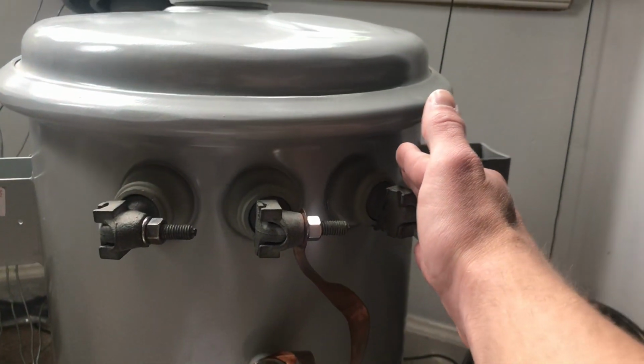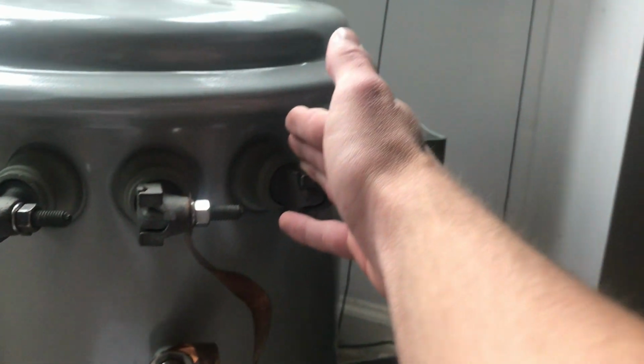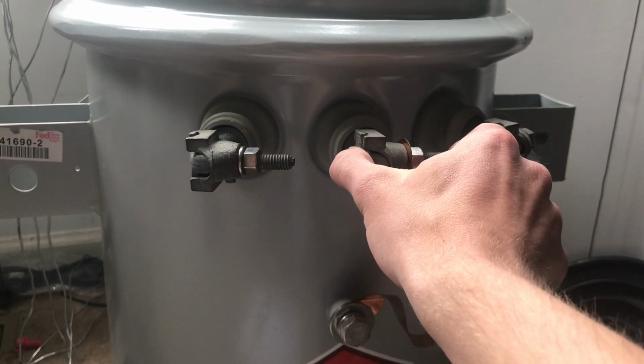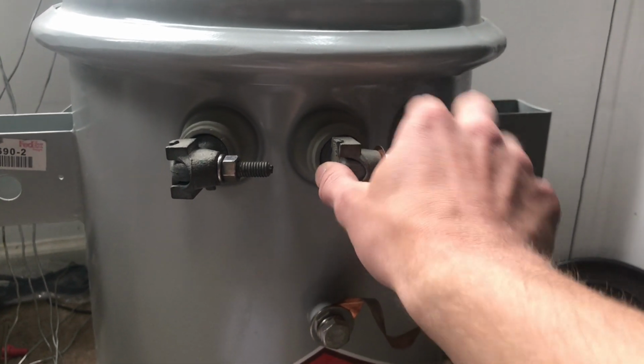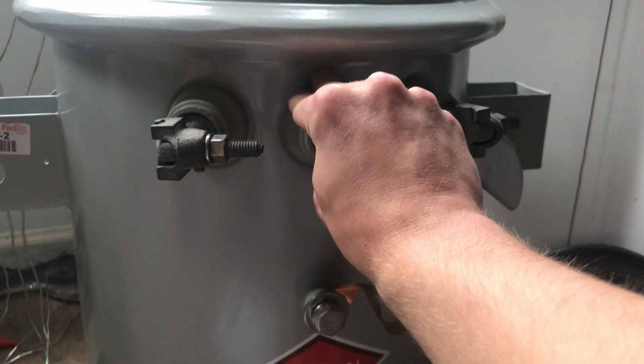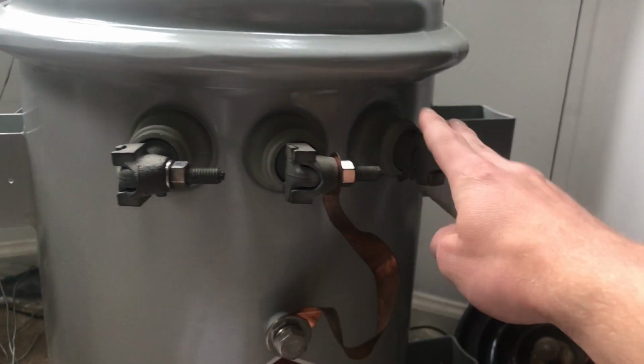120/240, and next to it they would tap off this bushing here, go to the second transformer, and then isolate this neutral here. So they'd put a cap over it, and this would not be touching ground, and then this would be the 208 leg. They would use two phases off the high voltage to do that.